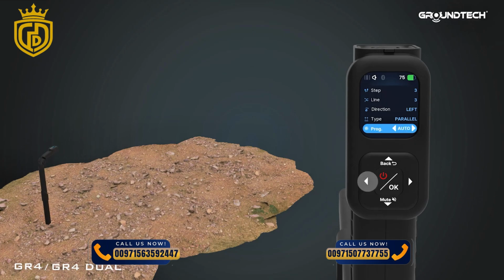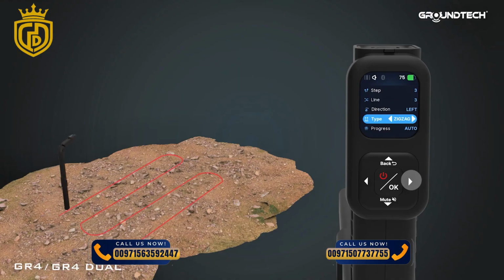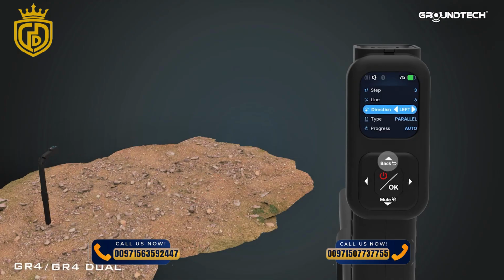You can perform a zigzag or parallel path. In the parallel scanning mode, The starting point of every line of the path should be right next to the starting point of the prior line and in the same direction. In the zigzag scanning, lines should be scanned in a back and forth manner. With the direction setting, you can set the starting point of the scan as bottom right or bottom left. When you start scanning from the bottom left, the next line of the path should be to your right. When you start scanning from the bottom right, the next line of the path should be to your left.